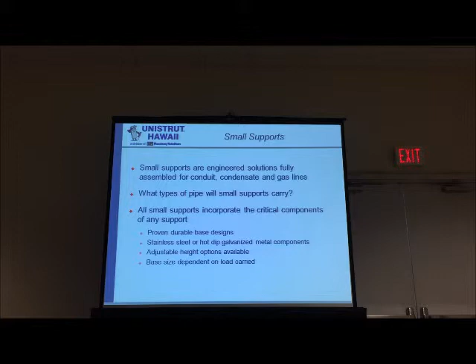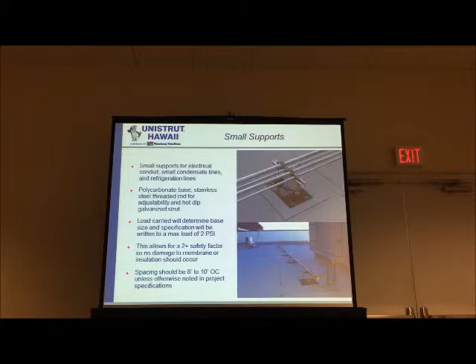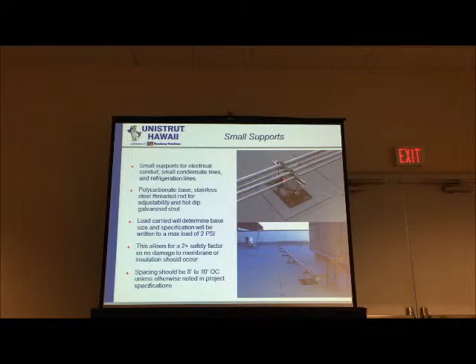So, small supports. What you want is, so you see this support right here, a nice firm base. You have a pad underneath the base, which is always recommended by the roof membrane manufacturer. They're always going to require that you have a pad underneath your support base. And so then here you have a wide enough support base. It's wider than the service that's being mounted. And you'll see that there's a piece of strut here with the pipe clamps. This looks very clean. It's very efficient. And you can see that over time, this is going to last a lot longer, better than some of the other supports that we've taken a look at so far.